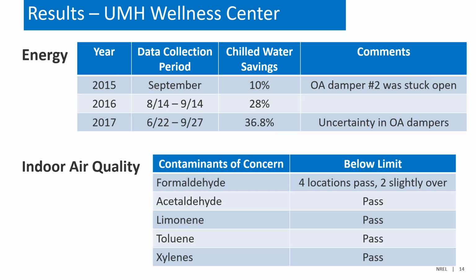All right, so the Wellness Center at the University of Miami. It's interesting because the first year in 2015, we saw about a 10% chilled water savings, but unfortunately, one of the dampers on one of the AHUs was stuck open, which drastically reduced our energy savings. The next summer, we had some good data for about a month period, and we saw 28% chilled water savings. And then the last summer, 2017, we saw almost 37% chilled water energy savings. So very good performance here. Obviously, there was some uncertainty in the damper position again, because we couldn't see remotely what the position was, but we saw very good performance.